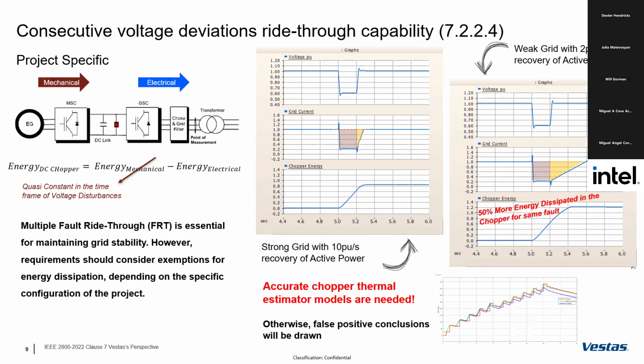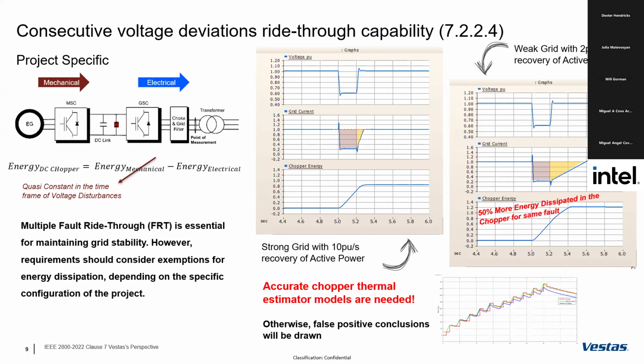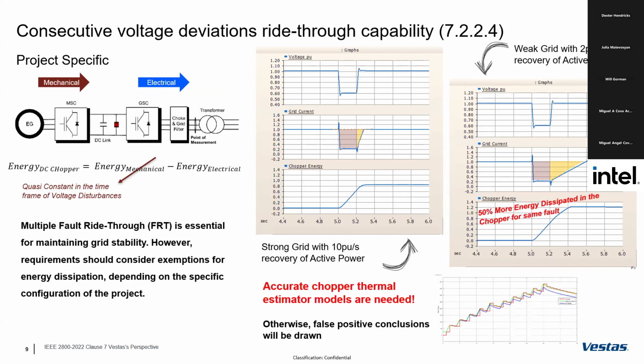that in some occasions, you might be compliant on the left-hand side when I'm operating in a very strong grid, because I can recover the power very, very fast. And the yellow shaded area is very small. So the chopper is burning energy during a very short period compared to the duration of the fault. However, if I try to slow down that recovery phase and then I recover slowly, then the chopper is actually being stressed significantly while the turbine is recovering. So the right-hand side, that is a project-specific configuration, might fail the same clause that a project connected into a strong grid will pass.